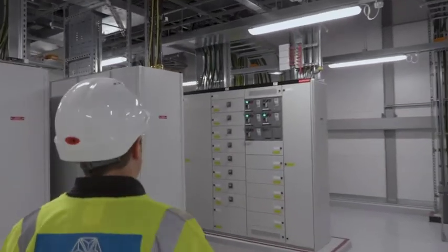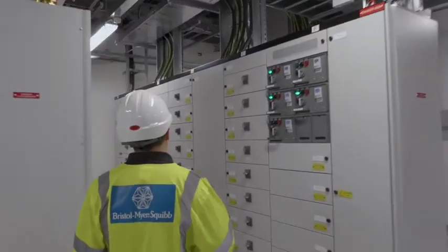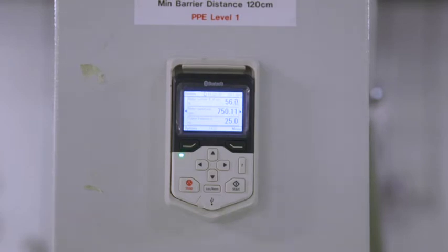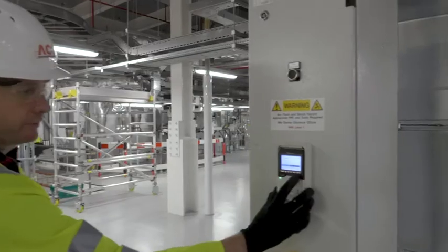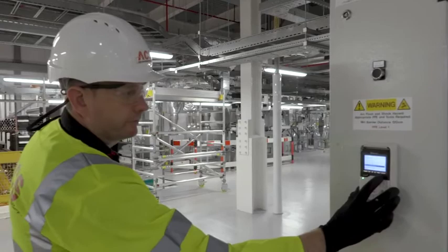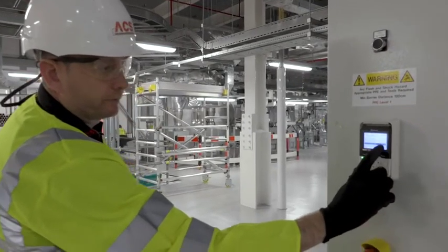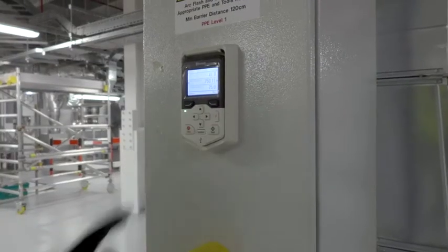BMS demanded that the system be configured for optimal efficiency. This is an example of one 11 kilowatt fan application running at 25 Hz while absorbing 56% current at the motor shaft. By entering the energy optimization group and triggering the flux optimization parameter, when we return to the main screen, a fall in motor current without affecting the process speed or fan performance has been achieved. In fact, the motor shaft power has reduced by 27% in this application.